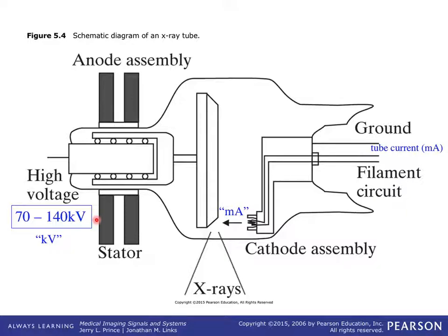Here's what the x-ray tube looks like. The anode and cathode are visible, with the electron beam going across, and a motor housing to spin the anode. The two controls on a fluoroscopy system are kV — the energy and wavelength of the beam — and mA — strictly the number of photons coming out.